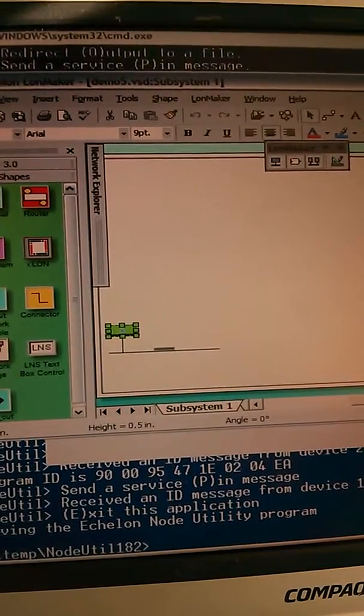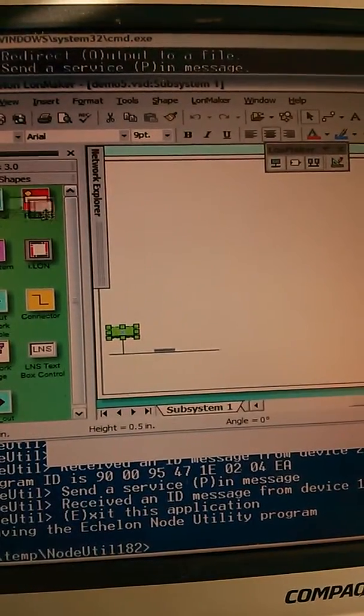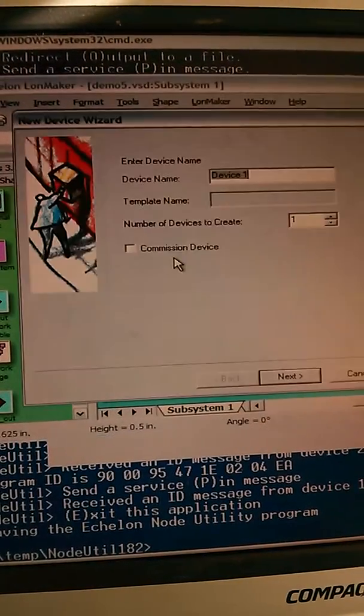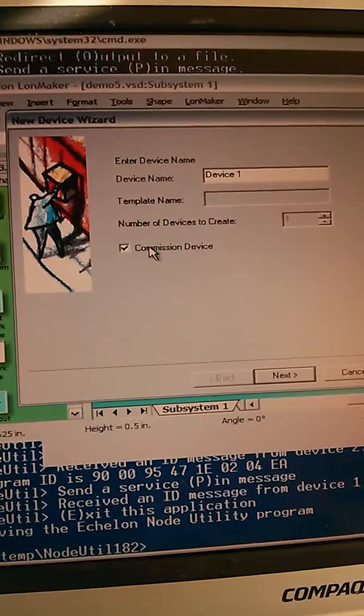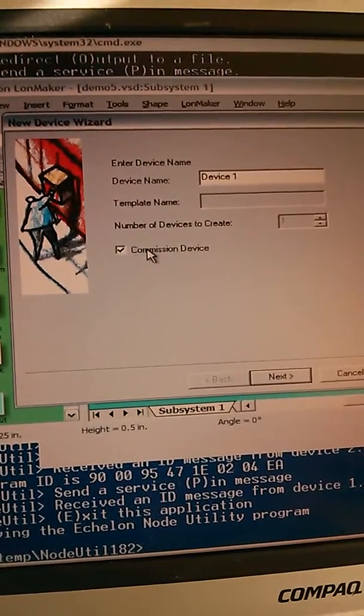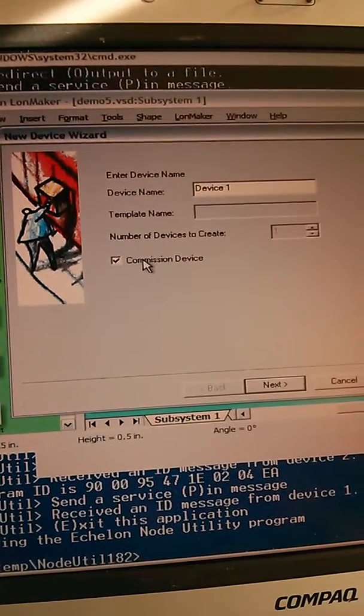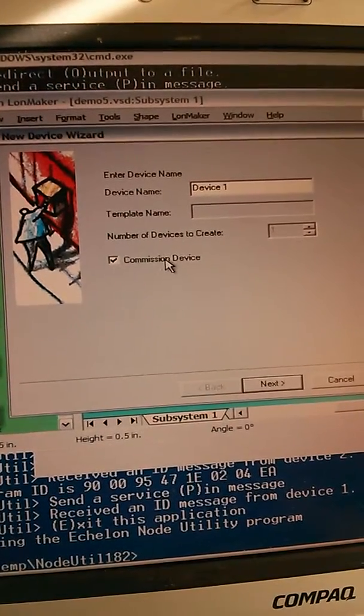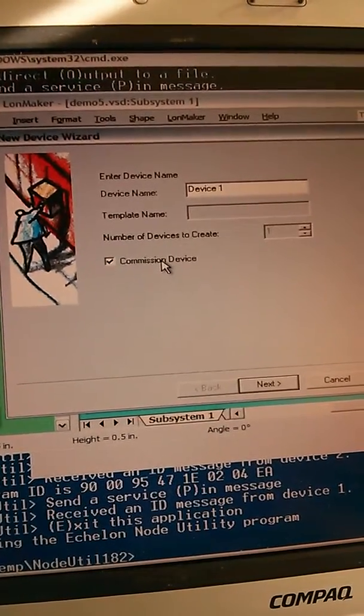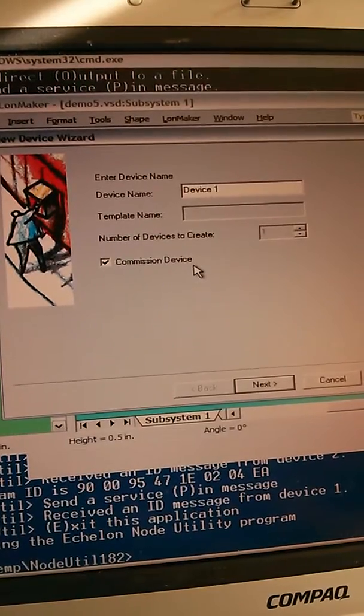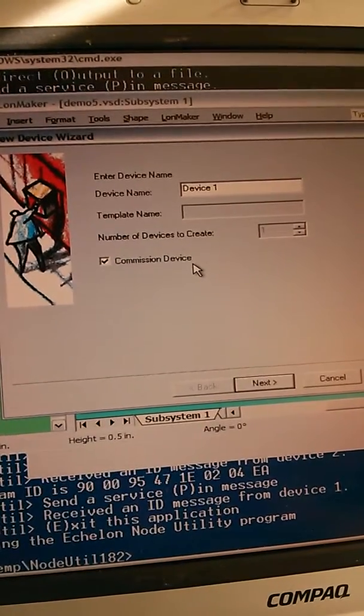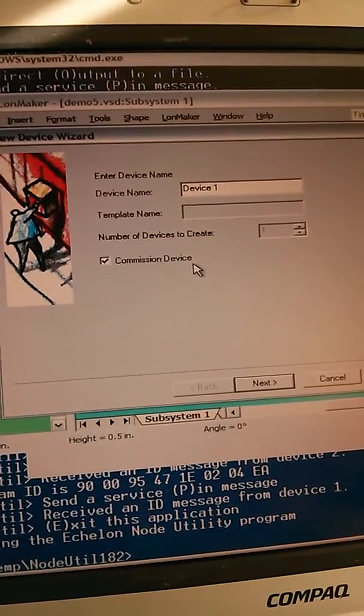In this step, I'm going to add another device. I'm going to commission the device. Commissioning is the process of allocating an address. An address in LonWorks consists of a domain, a subnet, and a node ID.